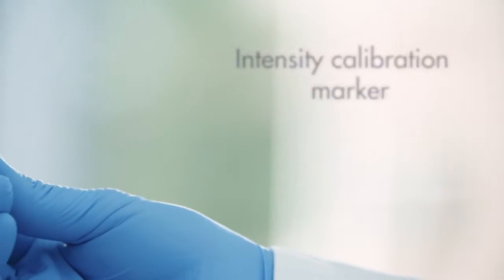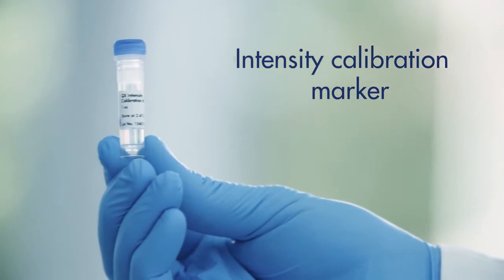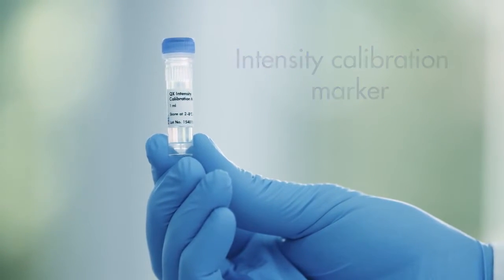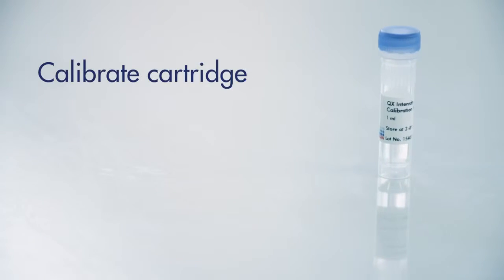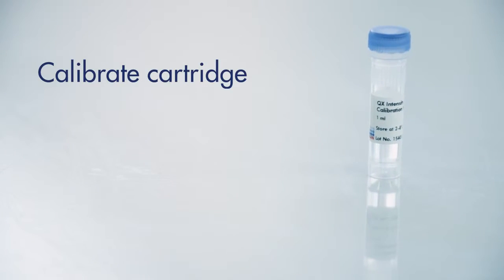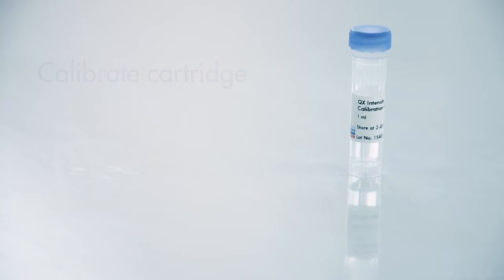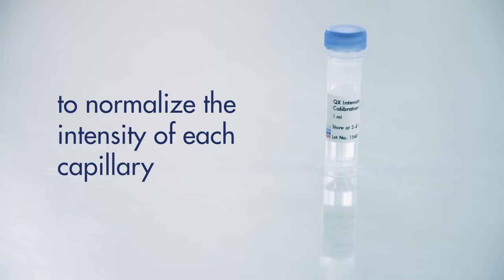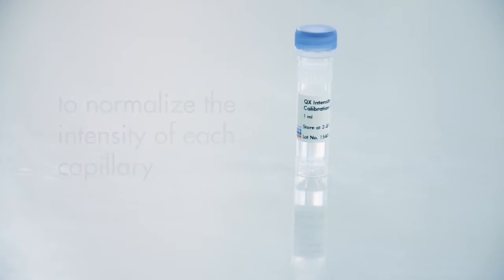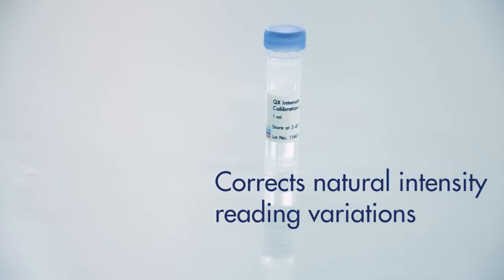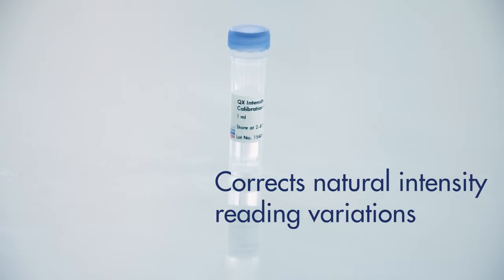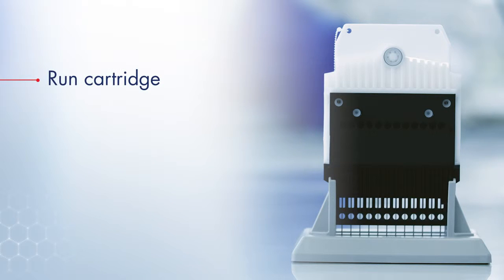Every kit is delivered with an intensity calibration marker, which is required to perform the calibration run. It is necessary to calibrate every QIAxcel cartridge prior to the first sample analysis to normalize the intensity of each capillary. This corrects for natural intensity reading variations between the capillaries in the cartridge. If you run a cartridge on another QIAxcel Advanced, it needs to be calibrated again. A cartridge can be calibrated up to 5 times.